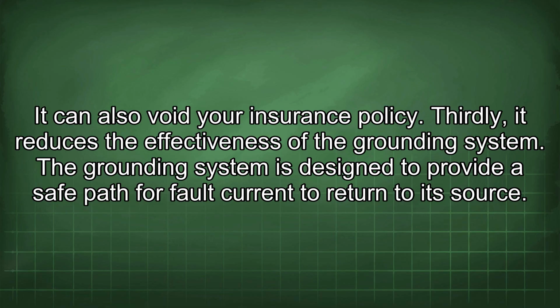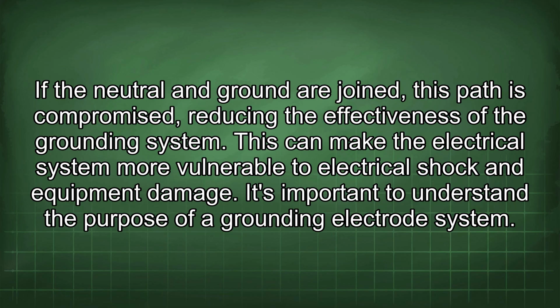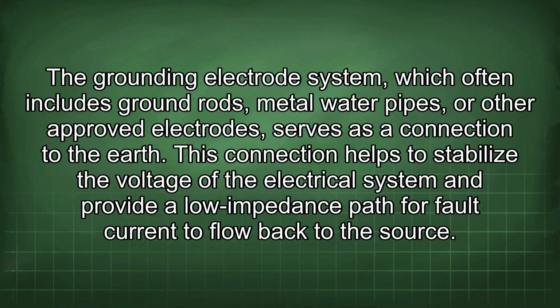Thirdly, it reduces the effectiveness of the grounding system. The grounding system is designed to provide a safe path for fault current to return to its source. If the neutral and ground are joined, this path is compromised, reducing the effectiveness of the grounding system. This can make the electrical system more vulnerable to electrical shock and equipment damage. It's important to understand the purpose of a grounding electrode system. The grounding electrode system, which often includes ground rods, metal water pipes, or other approved electrodes, serves as a connection to the earth. This connection helps to stabilize the voltage of the electrical system and provide a low impedance path for fault current to flow back to the source.